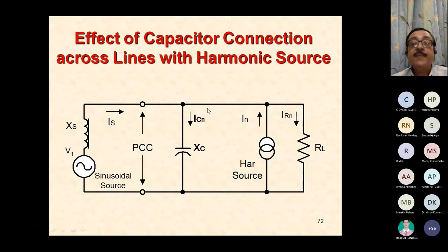Your argument was that this should have been the lower impedance, and whatever harmonic was flowing in the line should have got reduced, but now you find it has actually increased. And that is because unknowingly you have made a resonance situation with the source side reactance and your capacitor. So you must be very, very careful when you put the capacitor. It should not go into resonance with the source. You don't know the source reactance, so you have to make an estimate and observe and work very carefully without going into resonance. Otherwise, the input harmonic current will increase.